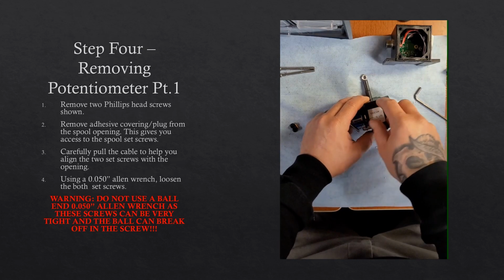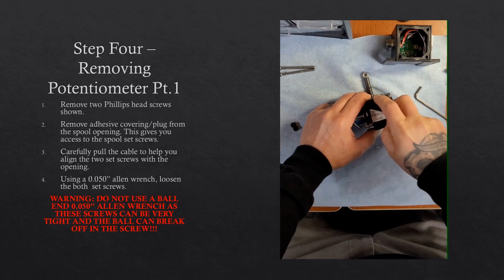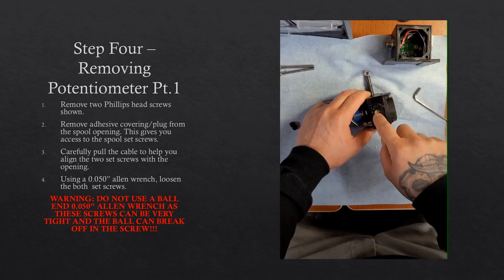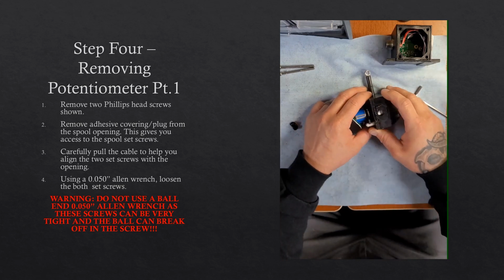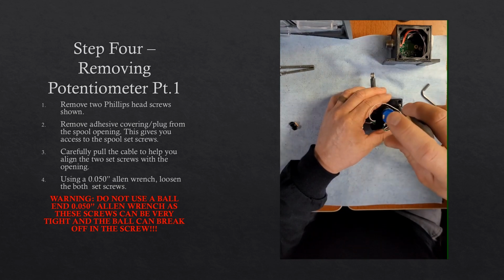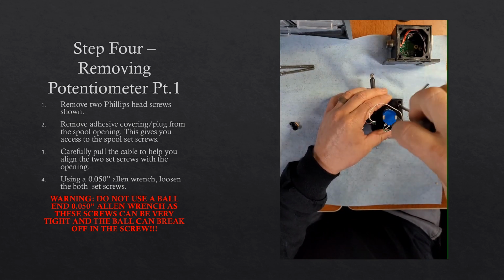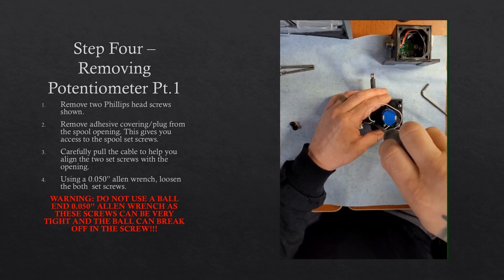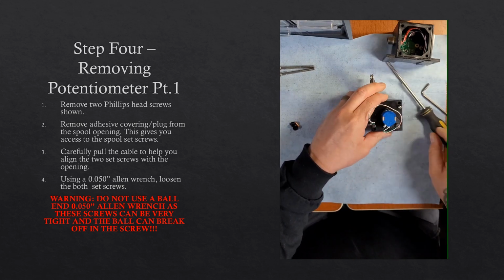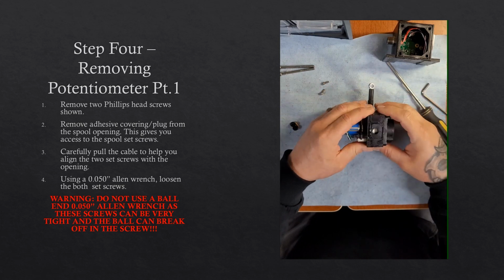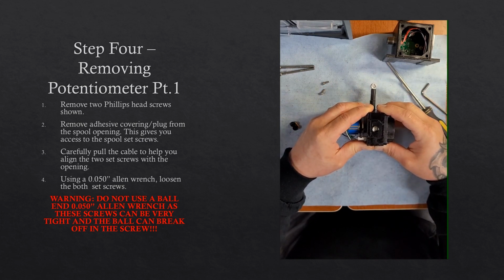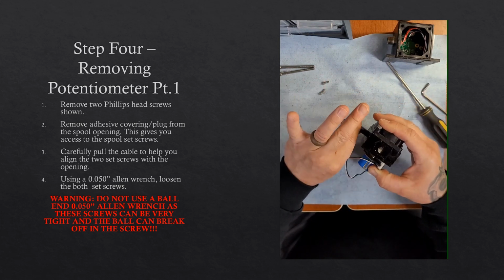Step 4, removing the potentiometer. First thing we're going to do is peel off that sticker. That'll expose the two set screws. Next thing we're going to do is remove the two Phillips head screws for the potentiometer plate. Once we get those two screws out, set them off to the side. You can see we can't separate it yet until we remove the two set screws.